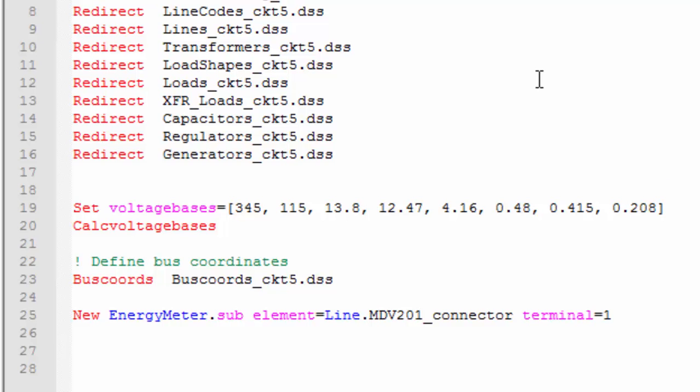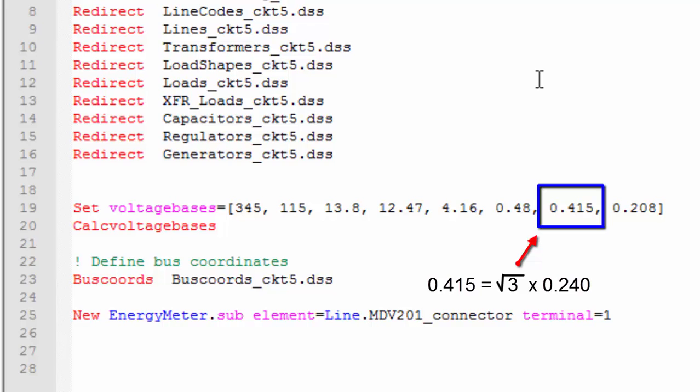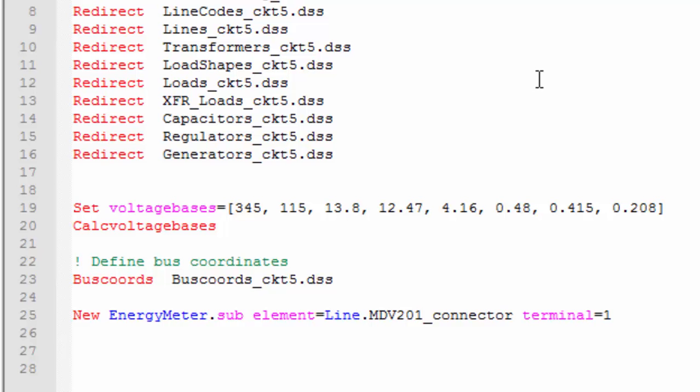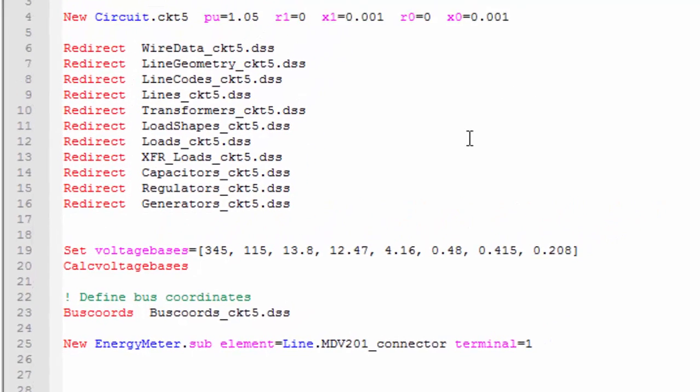Remember that the loads have been defined as 0.24 kV line-to-ground voltage, and the SETVOLTAGEBASES considers line-to-line voltages. Then, we need to define a voltage level equal to 0.24 kV times square root of 3, which is 0.415 kV. For more information about the voltage bases, please watch the voltage bases and solve video.